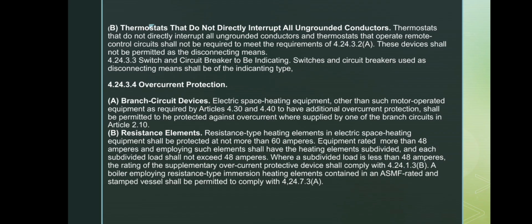B, resistance elements. For heaters using resistance elements: first, they must be protected at not more than 60 amperes. Second, if the equipment is rated more than 48 amperes, the heating elements must be subdivided and each section must not exceed 48 amperes. If any subdivided load is less than 48 amperes, the protective device must follow 4.24.1.3b. Last, boilers with ASME rated immersion elements may follow special rules in 4.24.7.3.